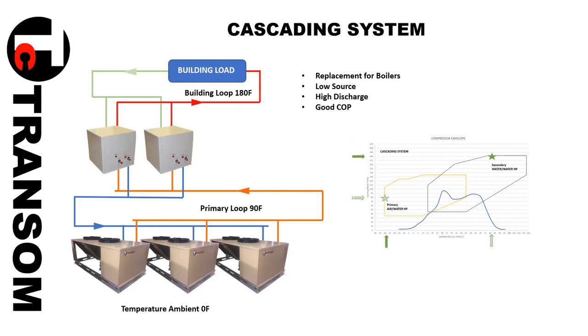But you have to work with what's available. Not a lot of compressors are UL certified for North American use with propane, and then there's the explosive part of it. Got it, thanks. But we are looking at it. Sorry, to finish off your question, we are looking at it, and the more we can do the higher end. We're still up at using R134a, which is a very good refrigerant from an application point of view, not from a GWP point of view.